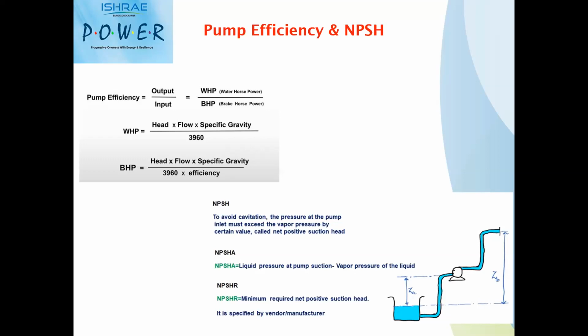So efficiency criteria generally are specified by the designers based on their overall plant efficiency designs and requirements. And as a pump supplier or pump manufacturer, we tend to select pumps within that efficiency range. And theoretically, the efficiencies are calculated based on head, flow, specific gravity, and your motor as well as VFD losses.